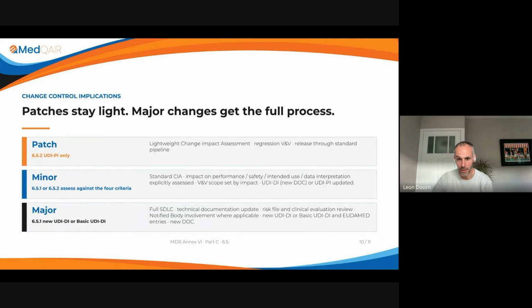EUDAMED. Finally, I think this has already been mentioned by both Monique and Stephen, but you have your patches, which are lightweight, maybe with some basic regression testing, and released through the standard pipeline, whereas for minor changes you would expect a larger change impact assessment, where you review what the performance, safety, and intended use changes potentially are. The data interpretation should also be explicitly assessed, and the V&V scope should be reviewed. And in my view, you get a new UDI-DI with a new DOC attached, or potentially a UDI-PI if you think that it doesn't affect the UDI-DI, which, again, I find really weird.